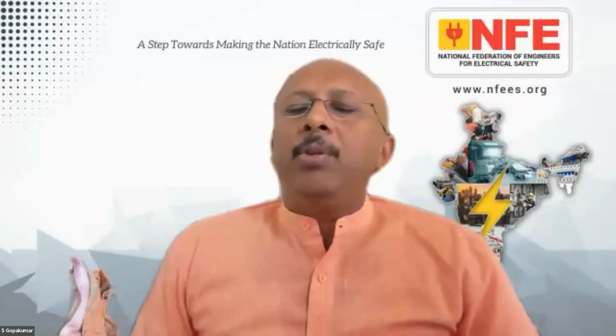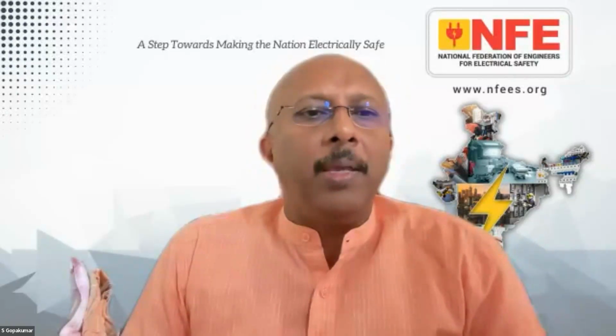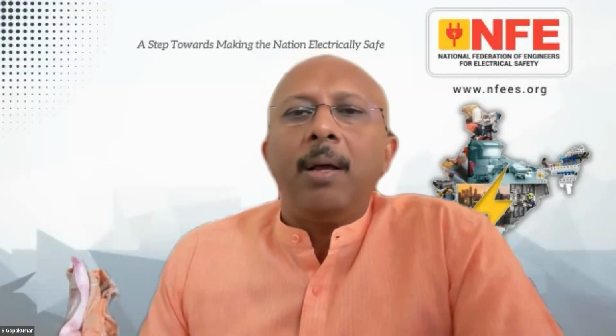Is it acceptable to use non-armored power cable for elevator power supply? I think there is nothing to do with armored. Armoring is just for mechanical protection. I think it's not to be confused with earthing or anything like that. Yeah, I think non-armored wires are allowed. Am I correct? Yeah, sure. No, actually, the IS calls for armored cables to be used, because of the glanding. When you are using armored cables, the glanding has to be used properly, both at the meter room and the distribution box for the elevator, so that you also have the alternative path, provided your main earthing conductors are available properly.